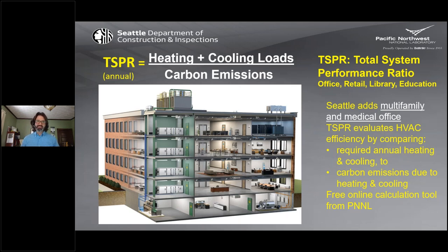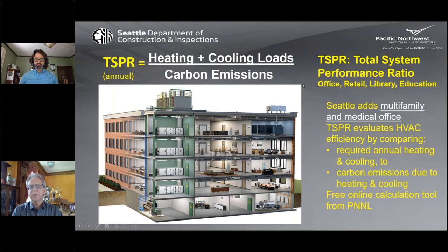Just want everybody to be aware once again that along with the entire mechanical section of the energy code, we've also got to do the TSPR, total system performance ratio calculation, to make sure that your carbon emissions in Washington State are not any worse than this pretty good building that we evaluated. This is going to be good, but it does take some attention, and going with an efficient heat pump system will almost always put you on the right side of that equation.